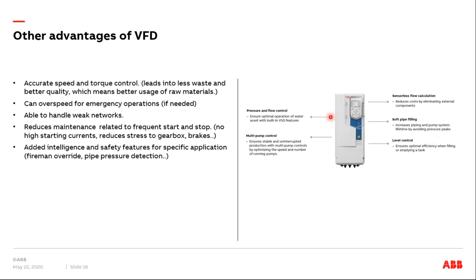And we have drives for HVAC applications, where for buildings and hospitals these kinds of drives are used. There you have features or intelligence so that if it detects fire, for example a lot of smoke or a fire in your building, the drive is able to spin the fan in the opposite direction and try to extract the smoke out of the building so that people are safe inside, or to minimize the damage that would be caused by a fire. So specific safety features and intelligence can be added to these drives.